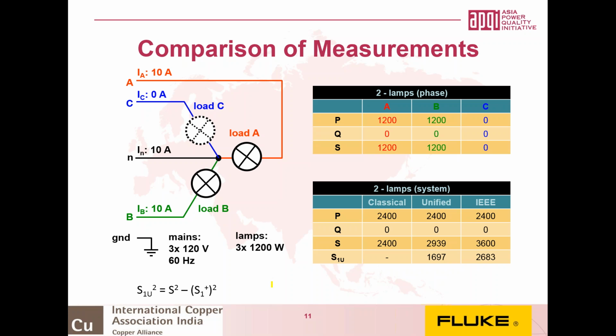So what's the best approach? Well, that depends on your point of view as much as anything. For an engineer, it's hard to see why the neutral current, which will flow through the branches, has to be multiplied by voltage that has no relation to it, as in IEEE 1459. The unbalanced power information in the unified method allows us to use passive unbalanced compensation techniques, while the IEEE 1459 method leads to unbalanced compensation that consumes more overall active power.